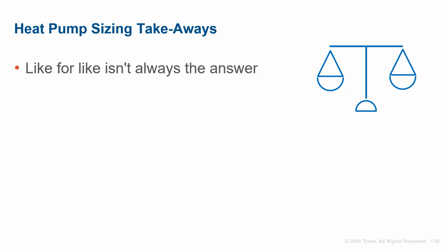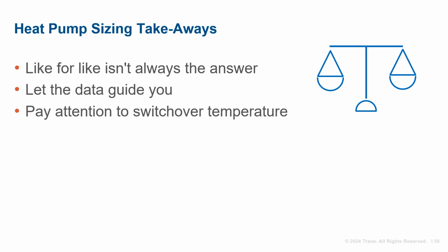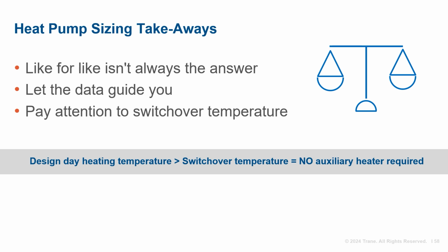So with this, there are several key takeaways. As with most things in life, kind of like a checkbook, there's a balance. Don't automatically replace an older HVAC unit with the same size. Energy efficiencies are changing at an ever-growing rate, and it could mean you could get by with a smaller system. Don't assume which way you will go if adjusting the tonnage because every situation is different. So use the data to guide you. Another way to help is to note the switchover temperature that Ray discussed earlier in the presentation. If design day heating temperature is above the switchover temperature and there's enough heat capacity, then no auxiliary heater is required.